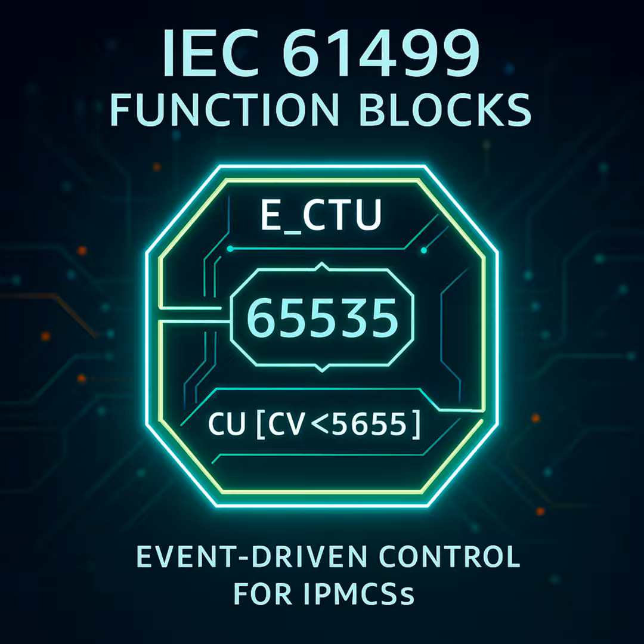So it's truly stateful, perfect for tracking things over the long haul, like total operating hours in a specific mode or number of times a safety interlock engaged. Absolutely. It remembers. And because this behavior, including that vital CV 65535 guard, is all defined by the standard, by the ECC logic, you get interoperability. Bingo. You can design your control application using ECTUs, and you have a high degree of confidence that if you deploy it on hardware from vendor A or vendor B, as long as they comply with the standard, that counter will behave exactly the same way, reliably, robustly.